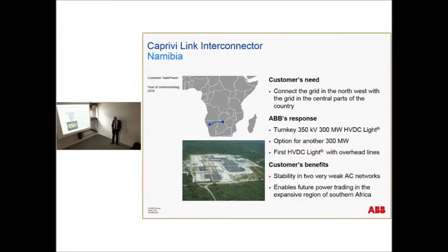In Africa, in Namibia, we have an HVDC light system of 350 kV, 300 megawatt. But this is what we call an asymmetrical system. So it can also be further developed to a symmetrical system with minus 350 kV, an additional 300 megawatt.